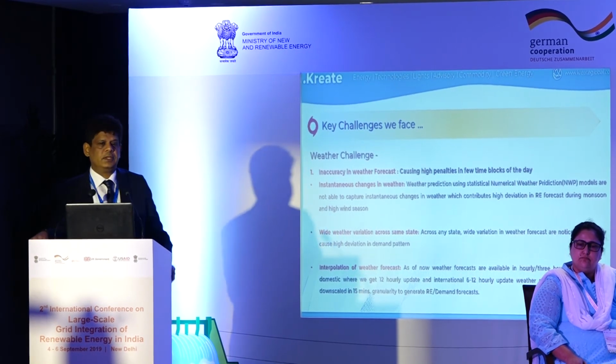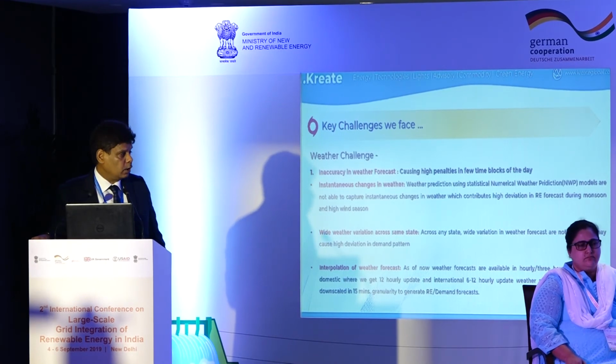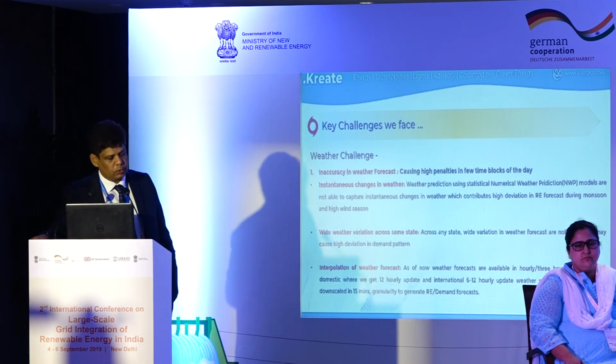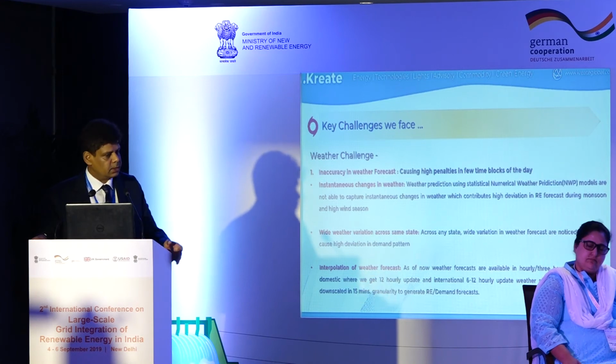Another challenge which we face is the weather suppliers. Now, weather data is available from all the 4 sources, which we're getting twice a day. That's it. Because for our revisions, we need it more often. And they come in blocks, where they either give us 3-hourly or 1-hourly data. So now IITM is giving us 1-hourly, and there are some others who are giving us 1-hourly also. But now we have to downscale it to 15-minute blocks. And that is when the difficulty of accuracy, especially on the sudden changes, happens.